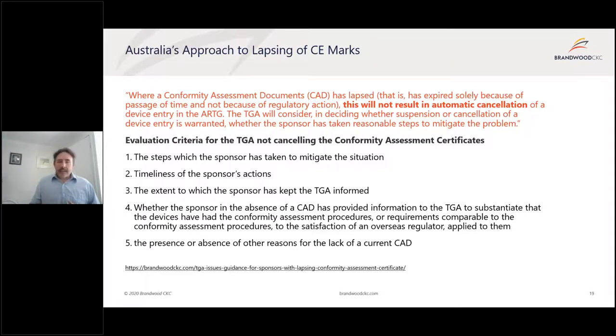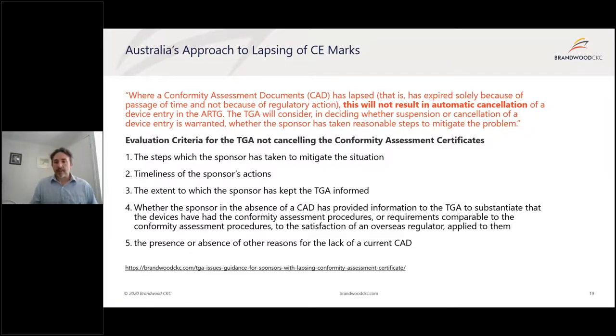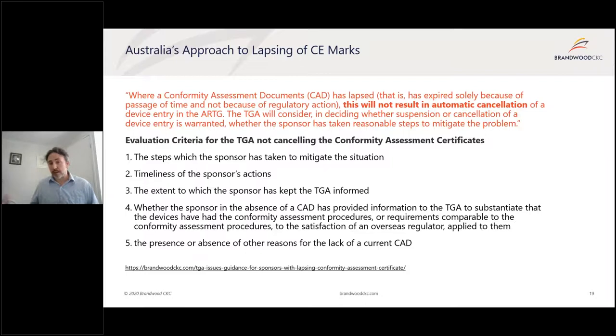To summarize TGA's approach: they are being pragmatic. They're not going to cancel registrations simply because a certificate has transitioned from MDD to MDR. They want to work with sponsors to ensure they're doing the right thing, with a clear plan and ongoing communication about progress. They will take steps to ensure timeliness of the sponsor's actions and assess whether overseas regulator information from other jurisdictions can be provided in lieu of a lapsing certificate.